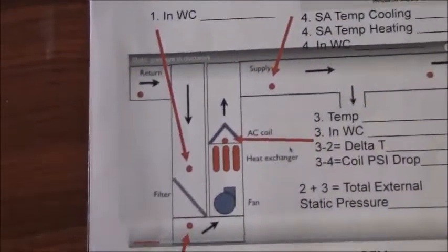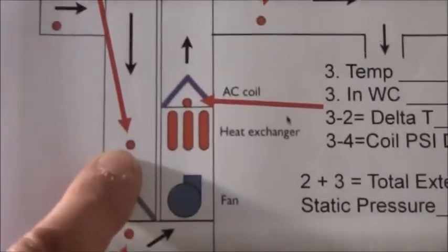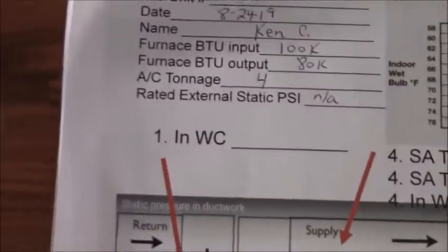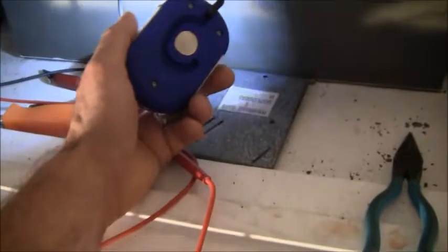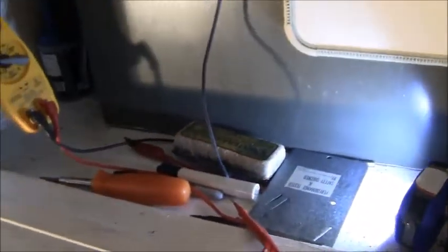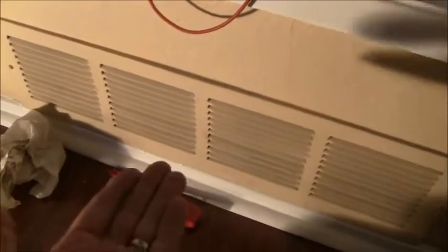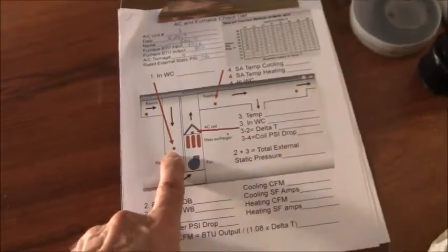Okay, so looking at my furnace chart, the first reading that I want to get is reading number 1, which is before the filter. I want to know what that is in inches of water column. I know that my filter is in the back of the door right here, because the air comes in and comes up. So I drilled a hole right there, on the other side of the plywood that this unit sits on. That is going to be the same thing as a pre-filter reading, because it's on the opposite side.